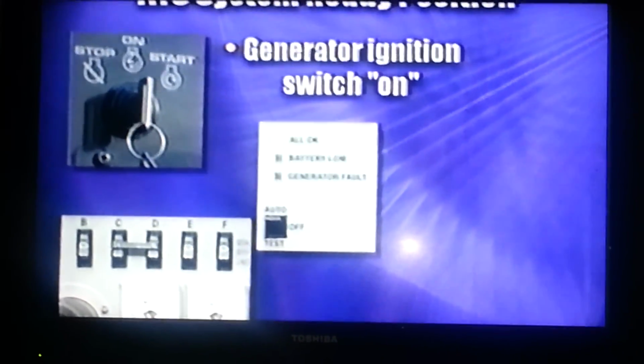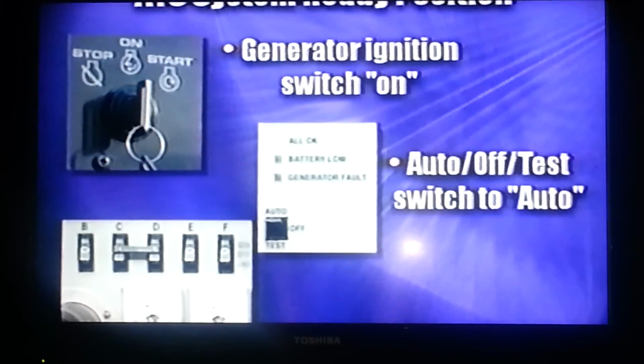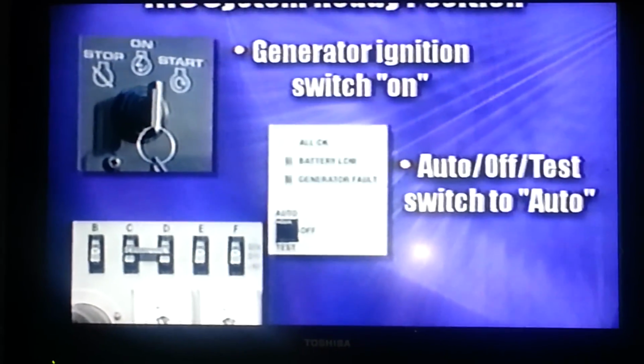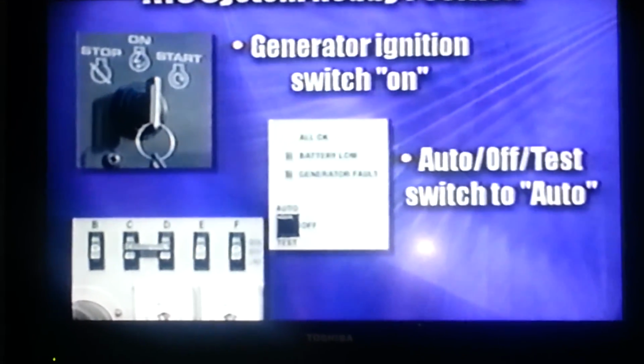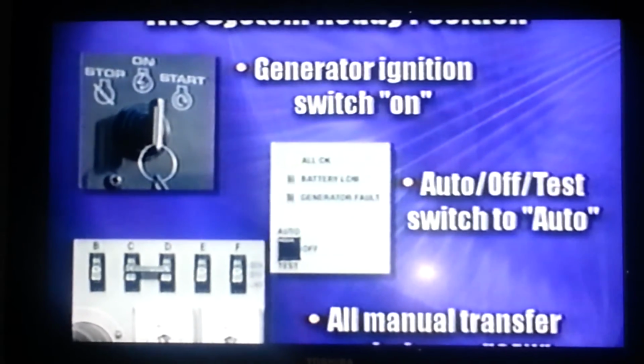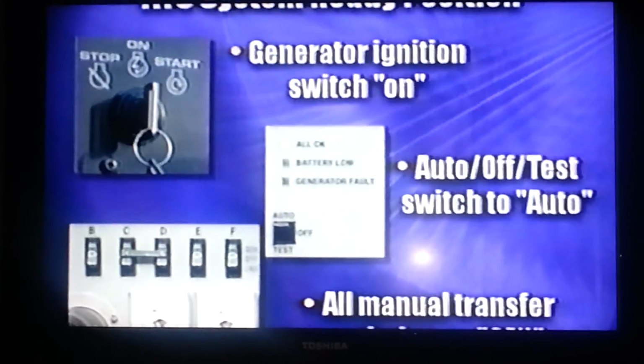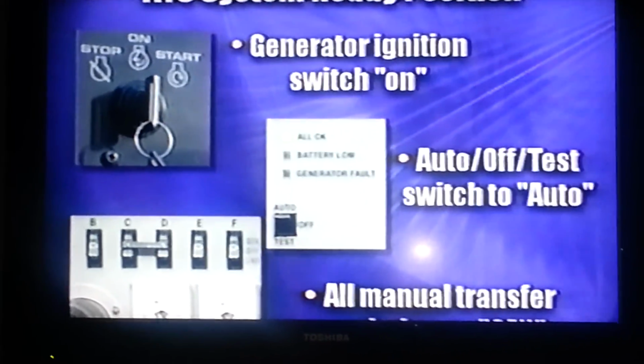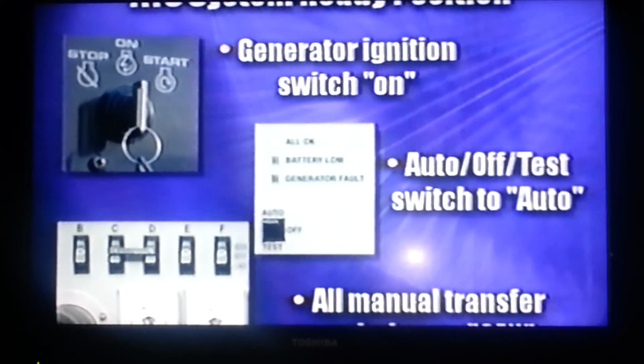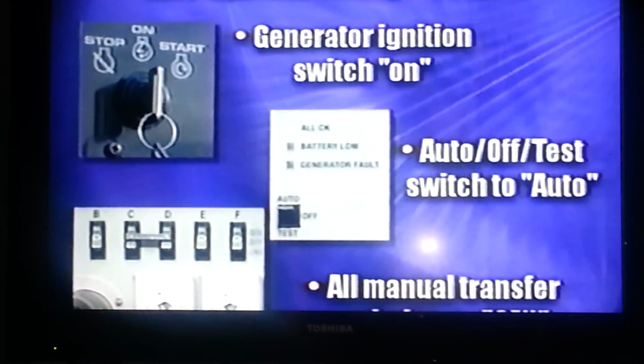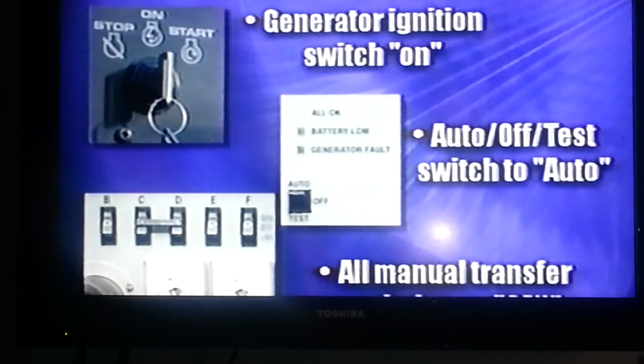Turn generator ignition to on. Move auto off test switch to the auto position so green OK light is on. Put all manual transfer switches to gen, depending on model of MTS or emergency supply panel. Refer to manufacturer specifications for appropriate settings.